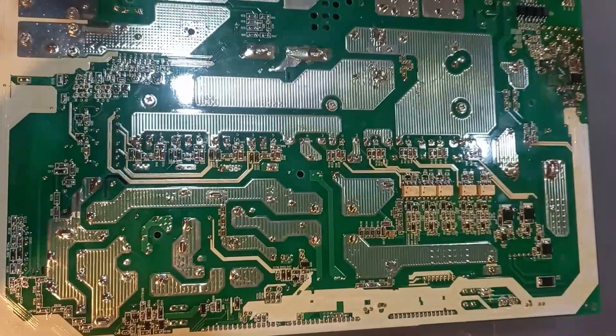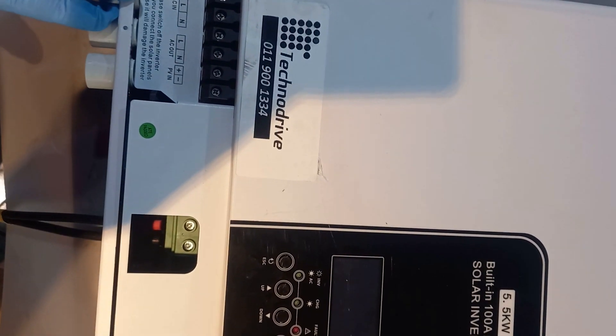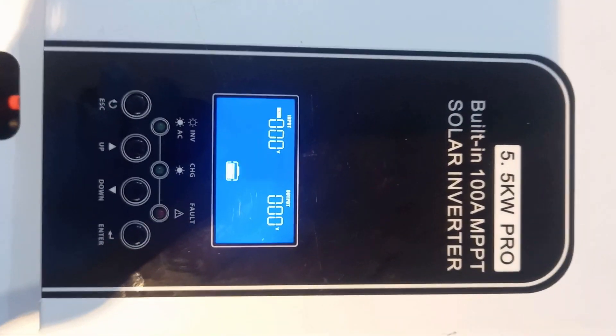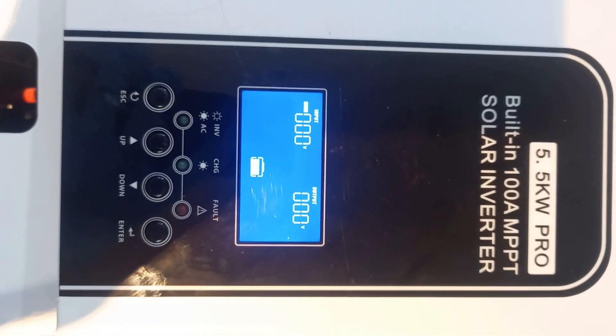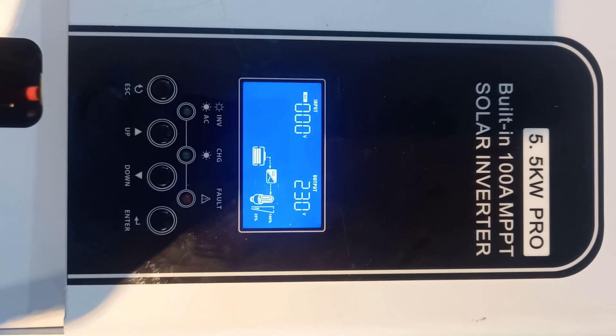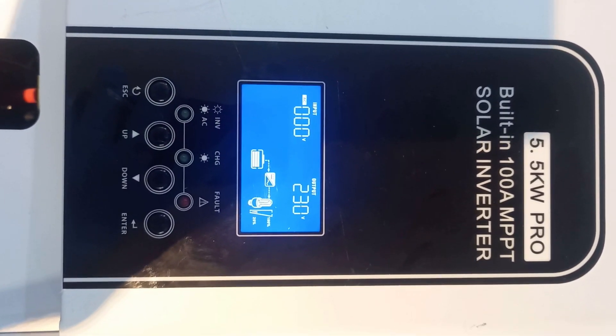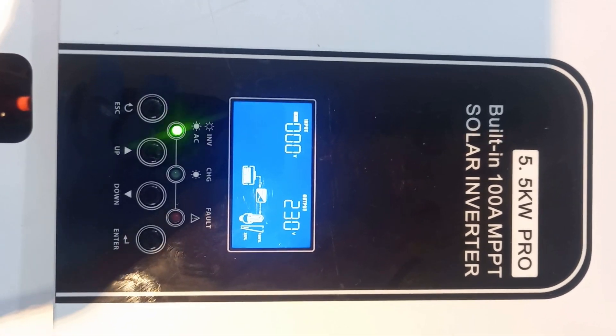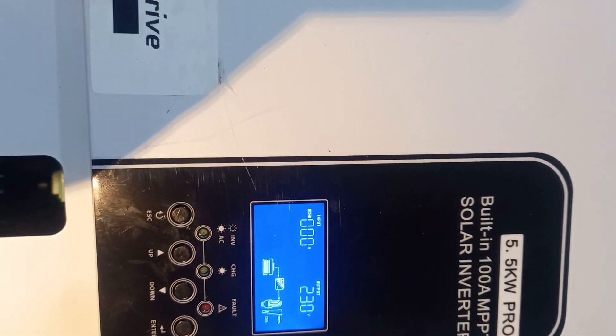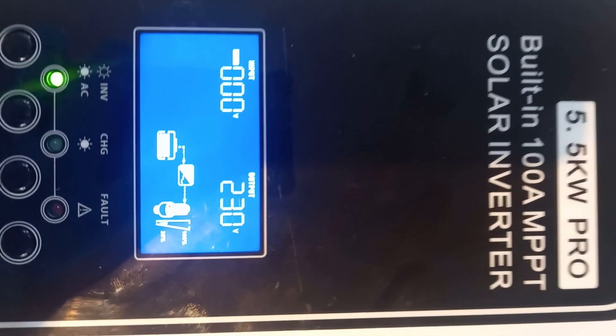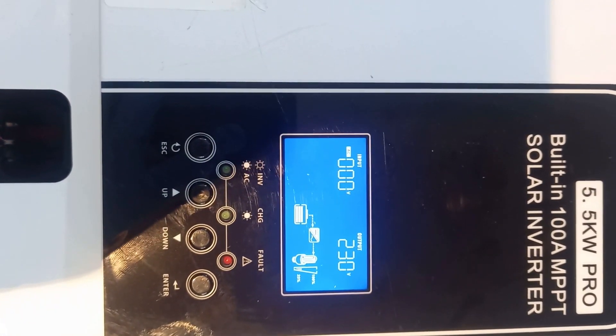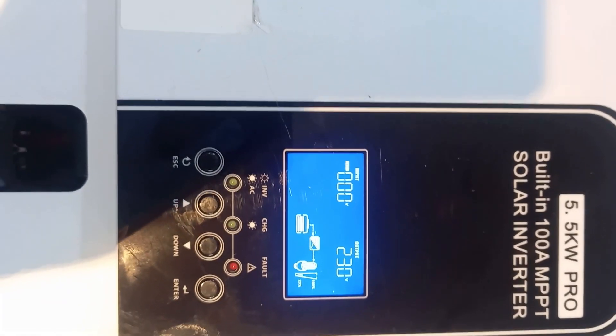We are now done with the repairs. The problem was on the input and output stage. You can see the inverter doesn't even take time - it's giving 230V output now and is no longer showing error 09. The problem was on the power board that I showed you before. The inverter is working 100% - it's just a matter of testing and making sure all the components are okay on the power board.